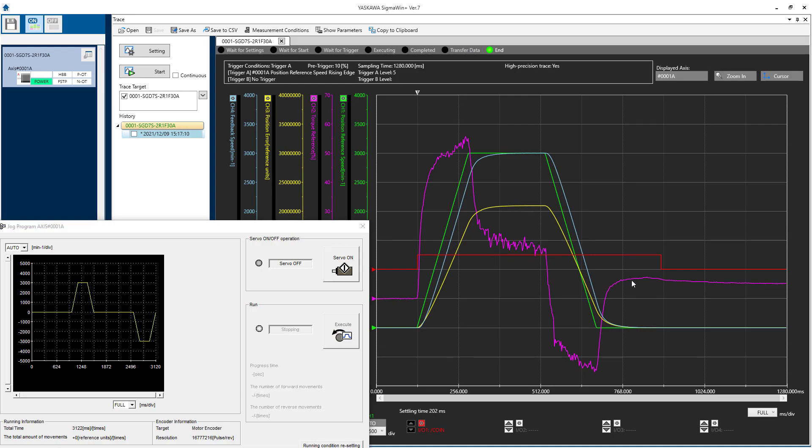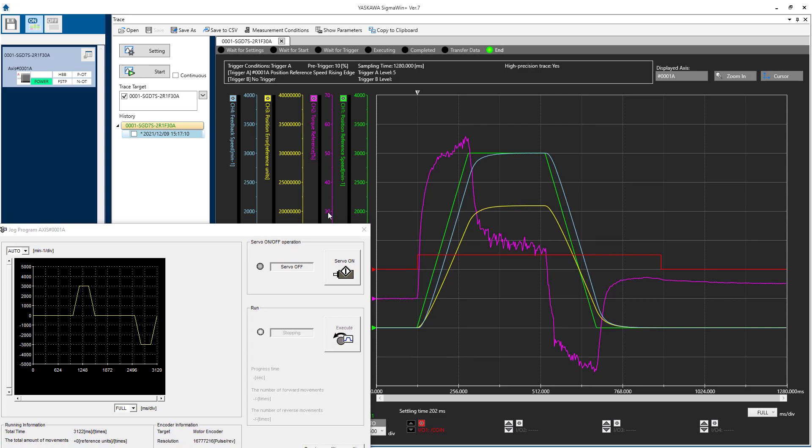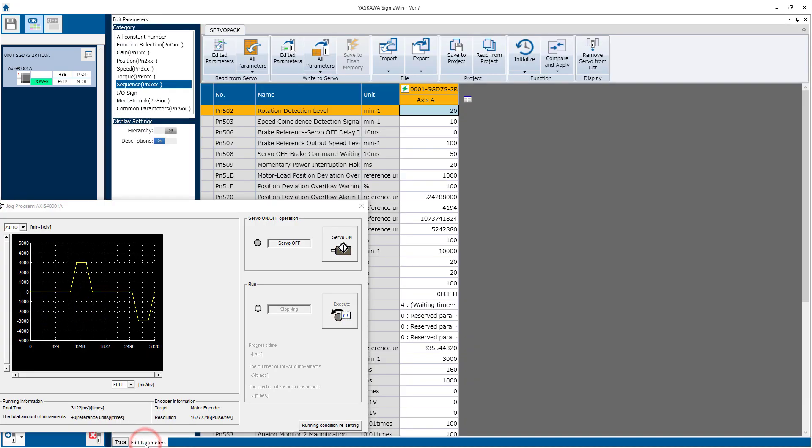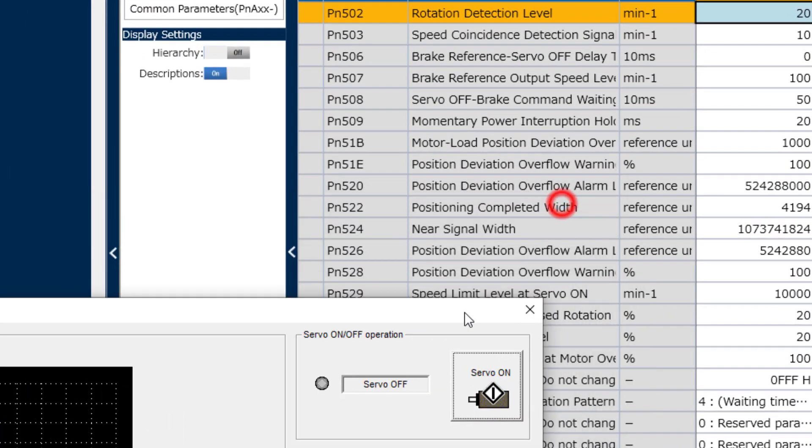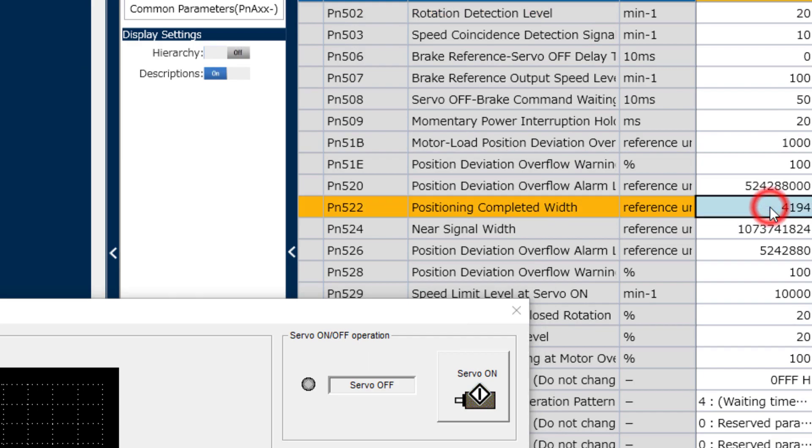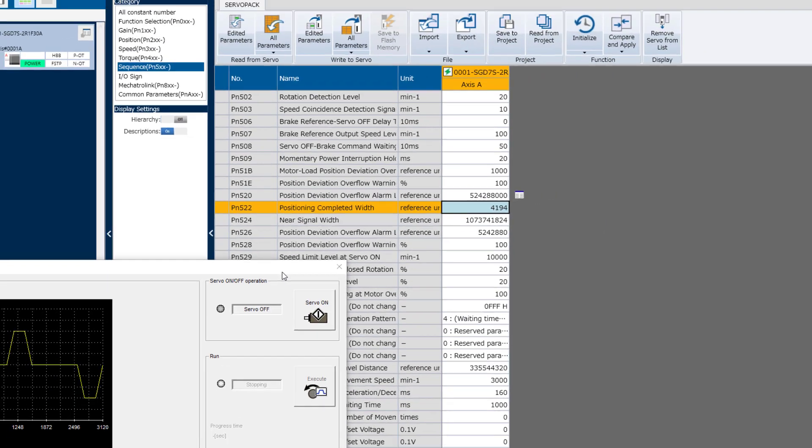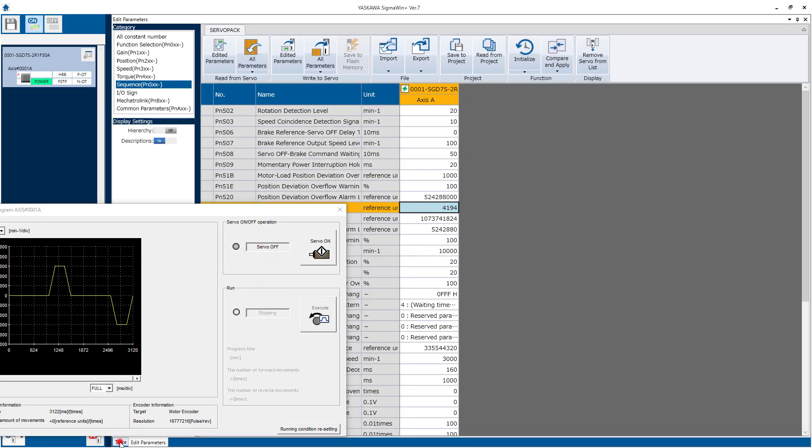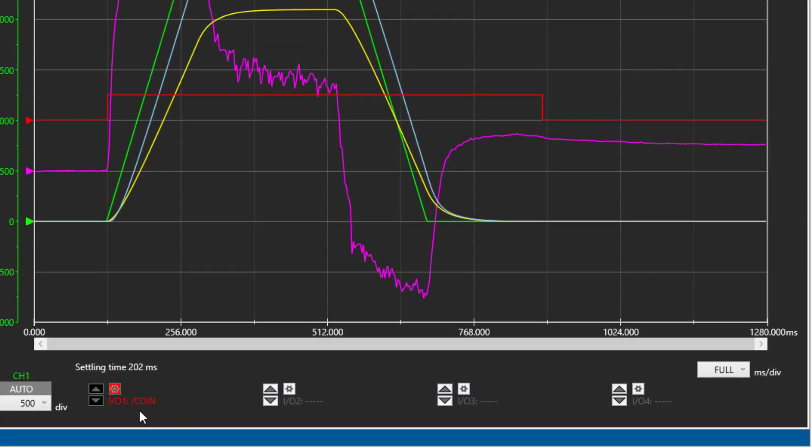For applications like this, you must determine at some point how much position error measured at the encoder will result in acceptable performance of the machine. So in this case, I'm going to use five thousandths of a millimeter, which is somewhat beyond the typical mechanical repeatability of a ball screw. That value converts to 4194 encoder pulses, which I've set to the Positioning Completed Width. And what that will do will make the /COIN position coincidence signal go low whenever the position error falls below that level.